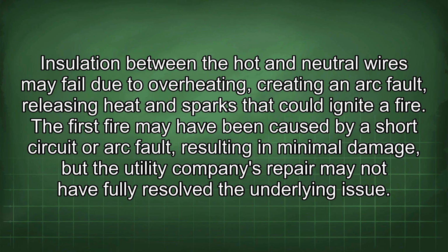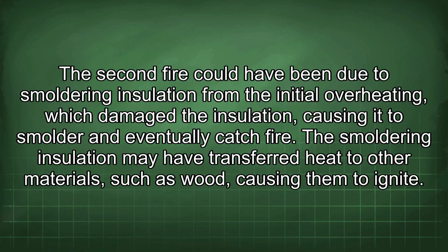The first fire may have been caused by a short circuit or arc fault, resulting in minimal damage, but the utility company's repair may not have fully resolved the underlying issue. The second fire could have been due to smoldering insulation from the initial overheating, which damaged the insulation, causing it to smolder and eventually catch fire. The smoldering insulation may have transferred heat to other materials, such as wood, causing them to ignite.